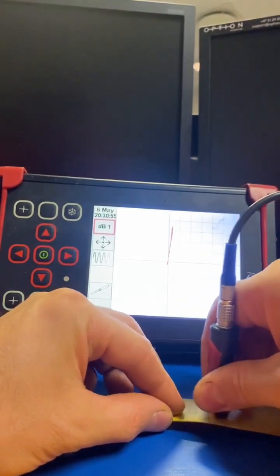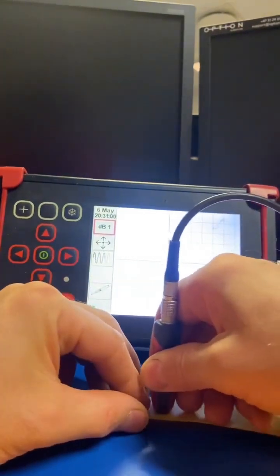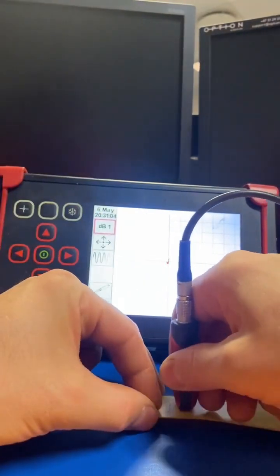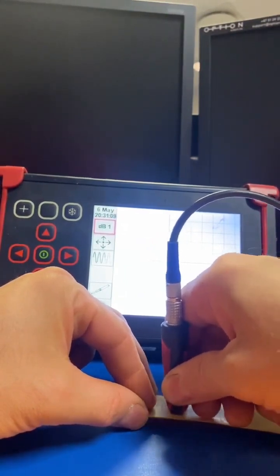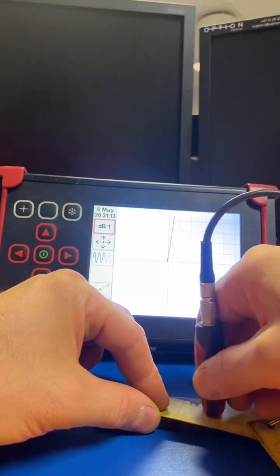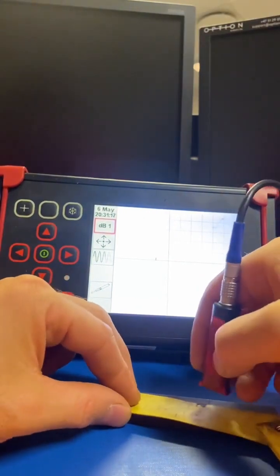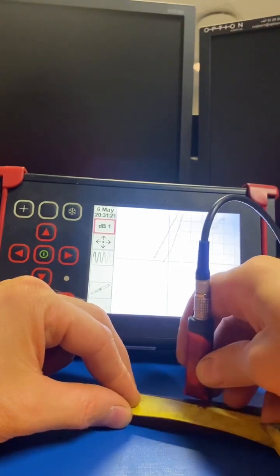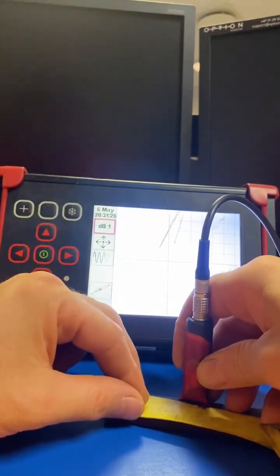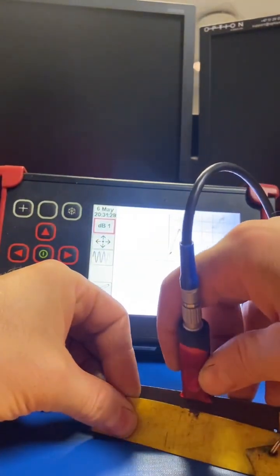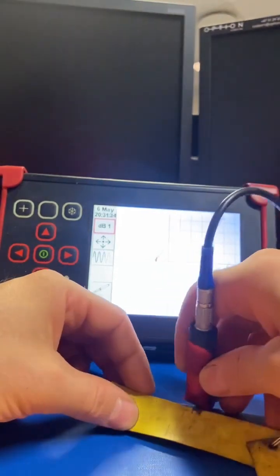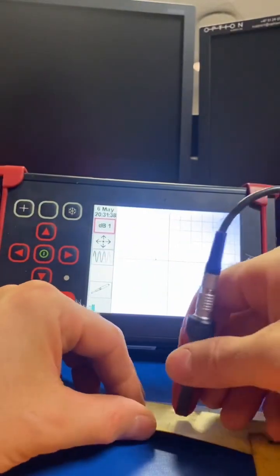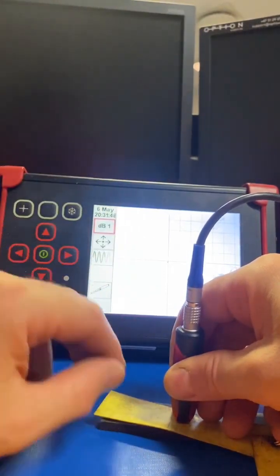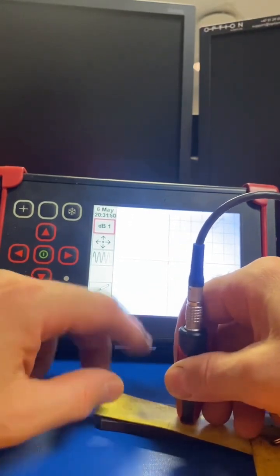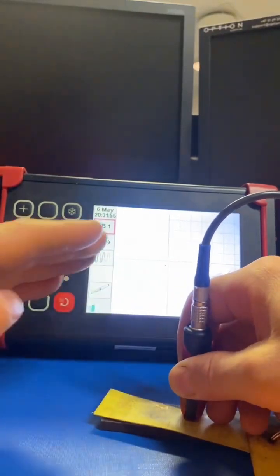Okay, you can clearly see the signal strength. It's currently around 80%. If we go on 0.5, it's a little bit smaller signal, around 40%. And 2 mil is around 100%. But when you are scanning and you go onto the edge, it clearly shows a very significant signal. This edge, because it's thinking that this is a crack indication. That's why cracks always look like that. More like this. If it is like an 8, it means not a crack, it's just a false signal. You will often see on the job a lot of various edge signals, but the actual crack will typically be a straight signal like that.